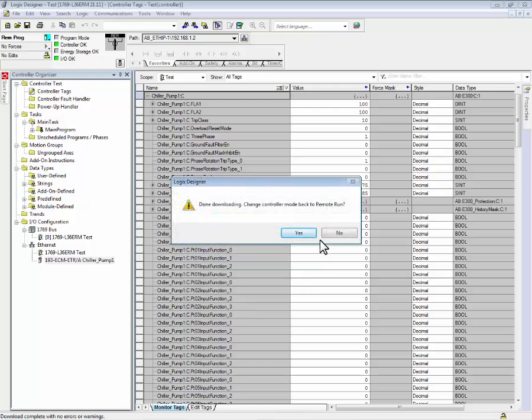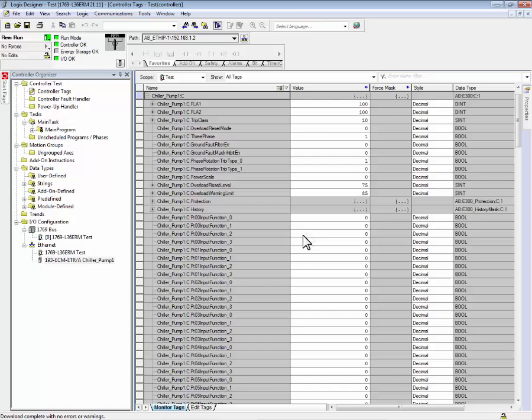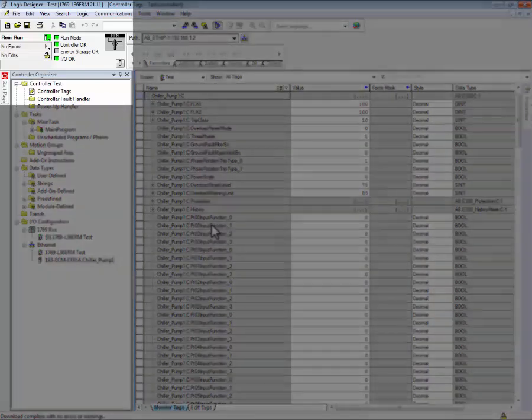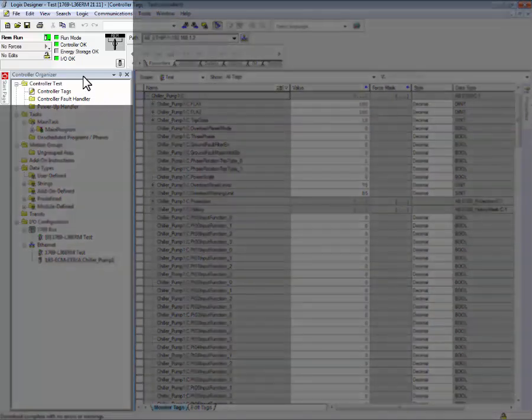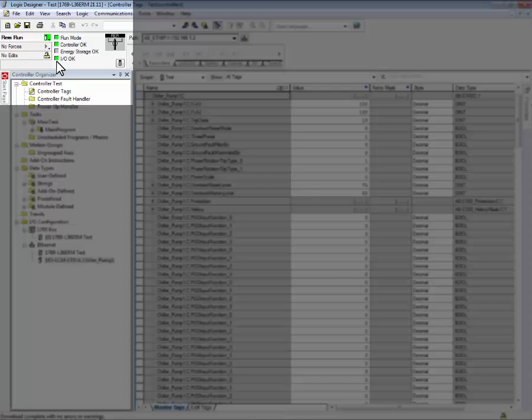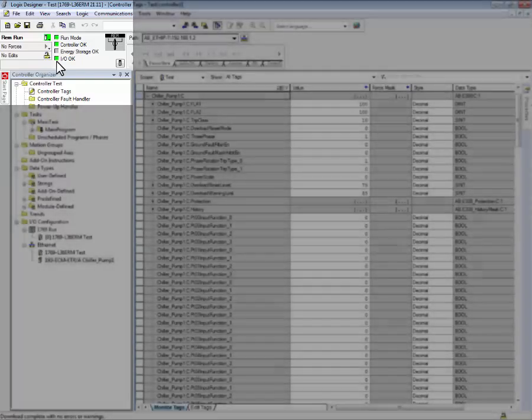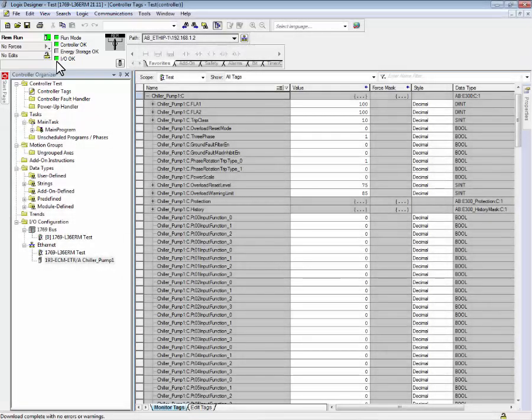To begin communications between our Logix controller and our E300 electronic overload relay, we will put the controller back into run mode. As you can see, the IO OK data indicator is solid green, which means that the Logix controller is successfully communicating to our E300 electronic overload relay.